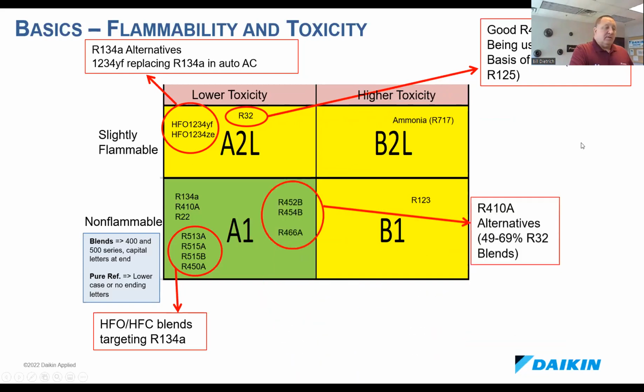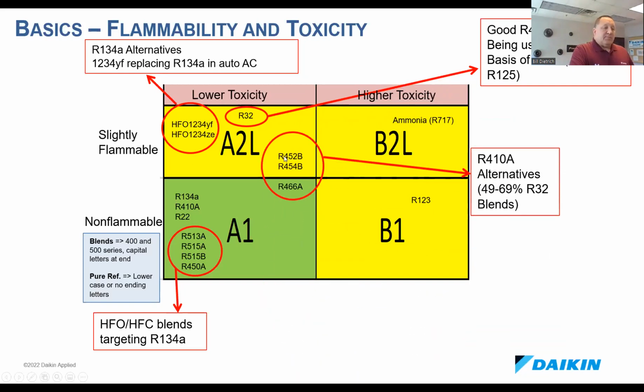in new equipment. And then the other one that's garnering the most interest, probably the one you'll see the most of, is R454B. There's a 452B, but the 454B is the one that's probably more likely. And again, these are mixtures. They have generally from 50 to 70% R32 with some other things in them. And they're blended to be similar in displacement to what the 410A was, to make a transition to that product a bit easier.